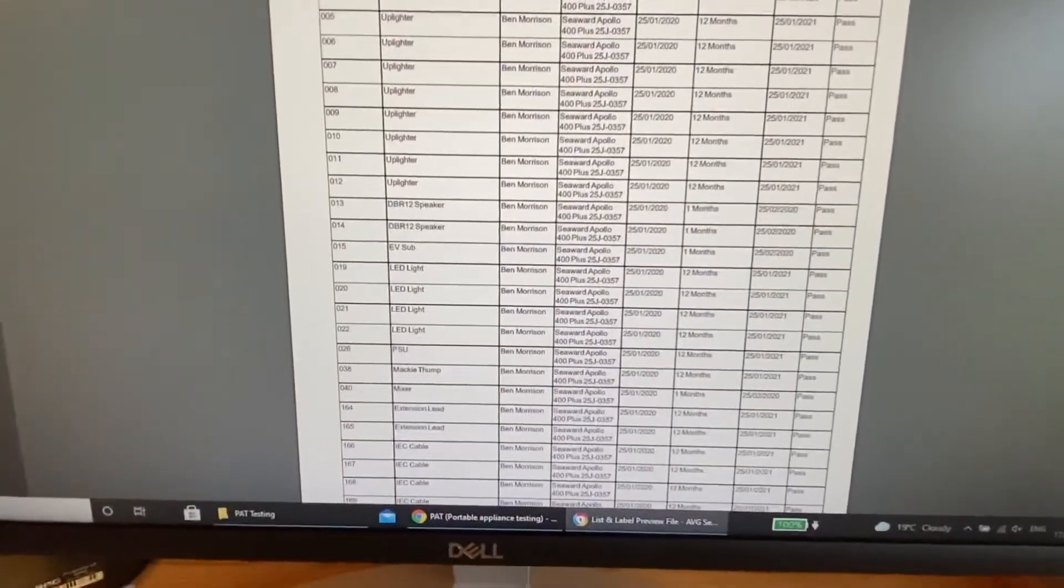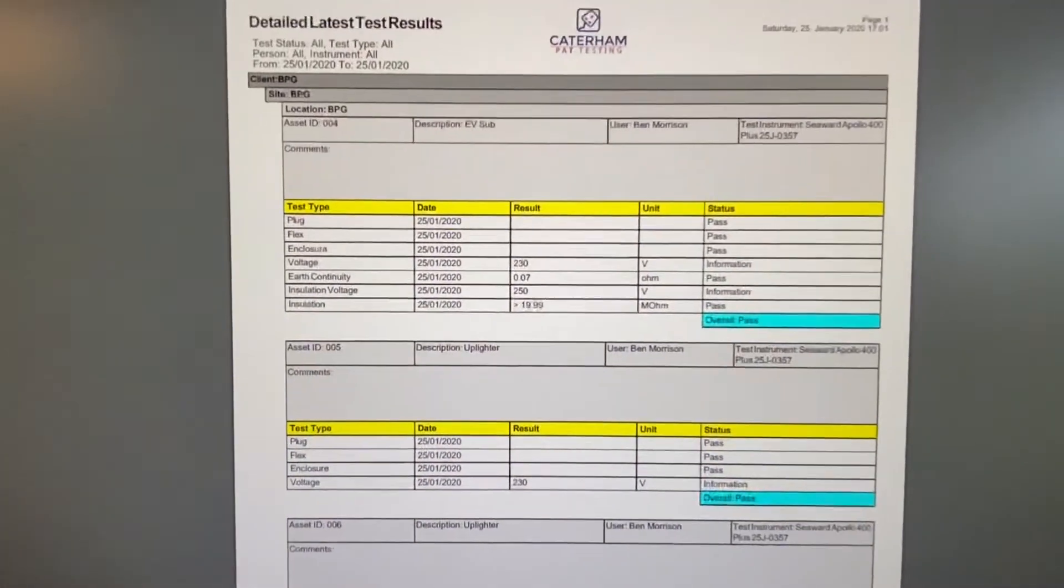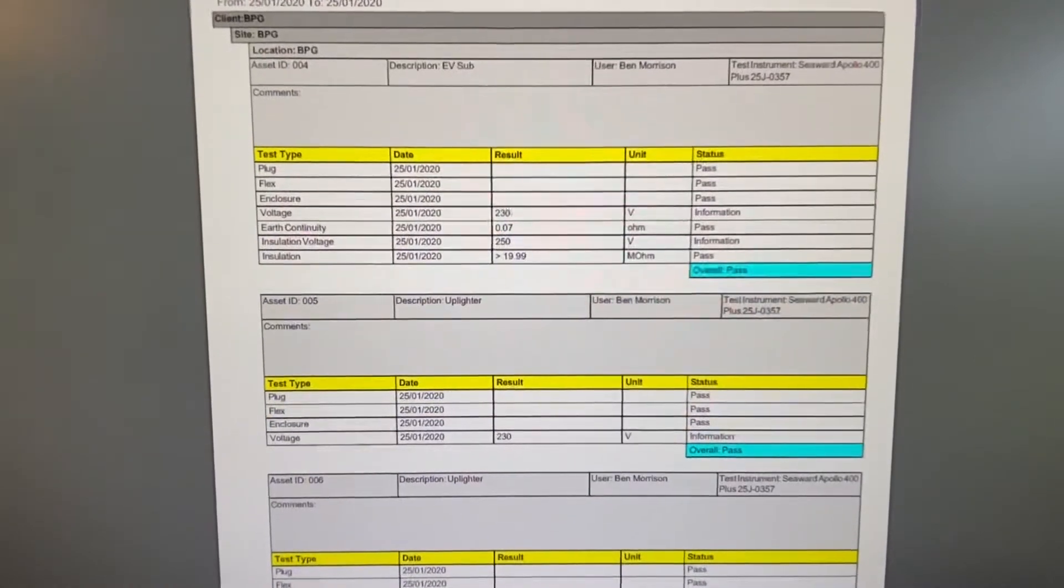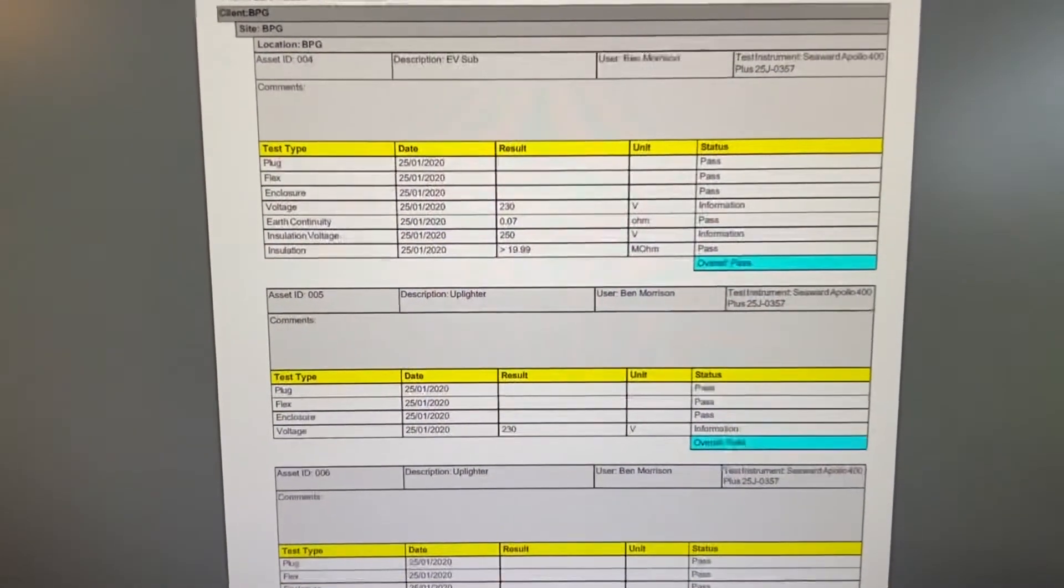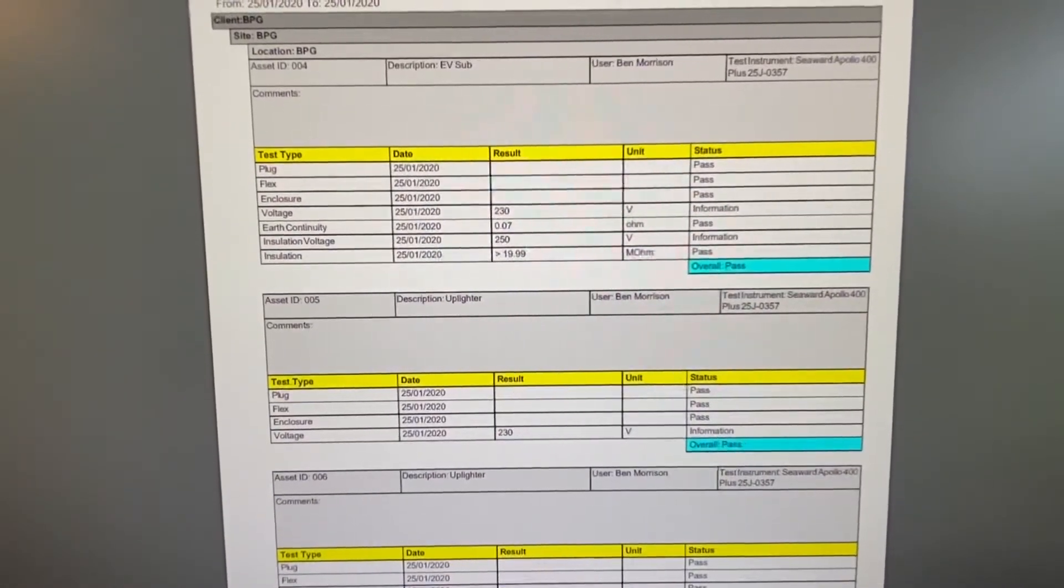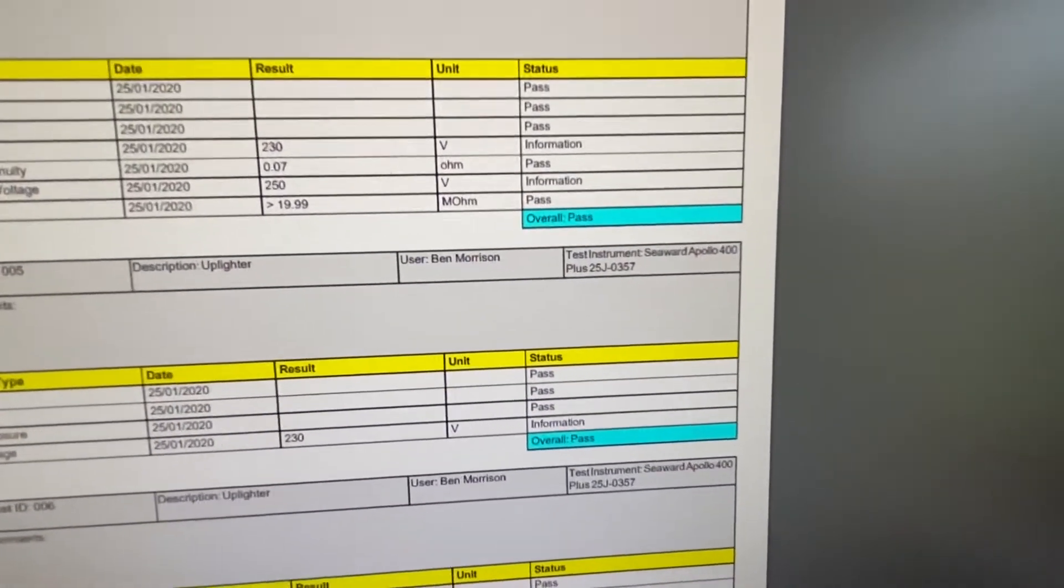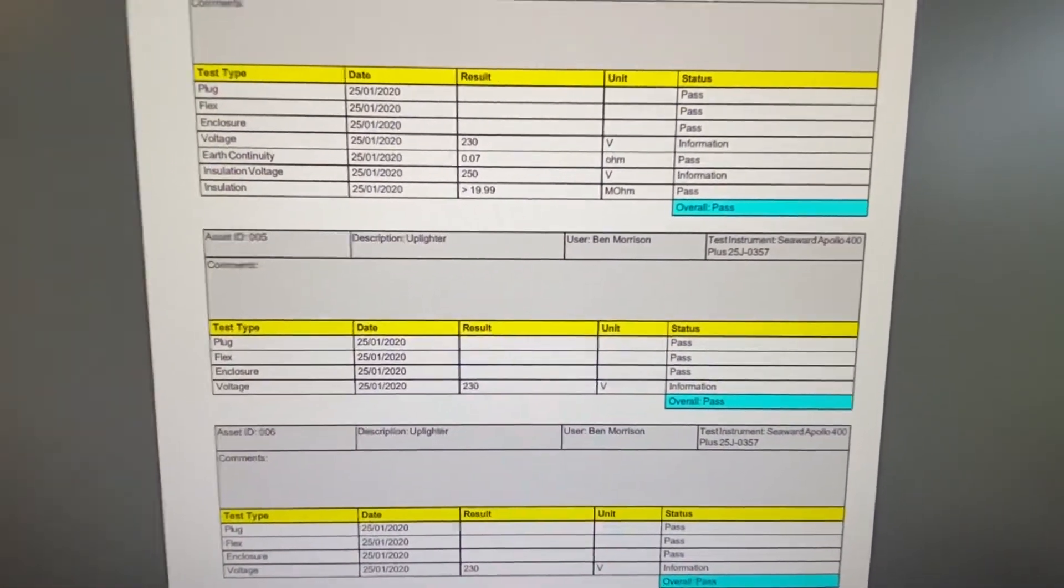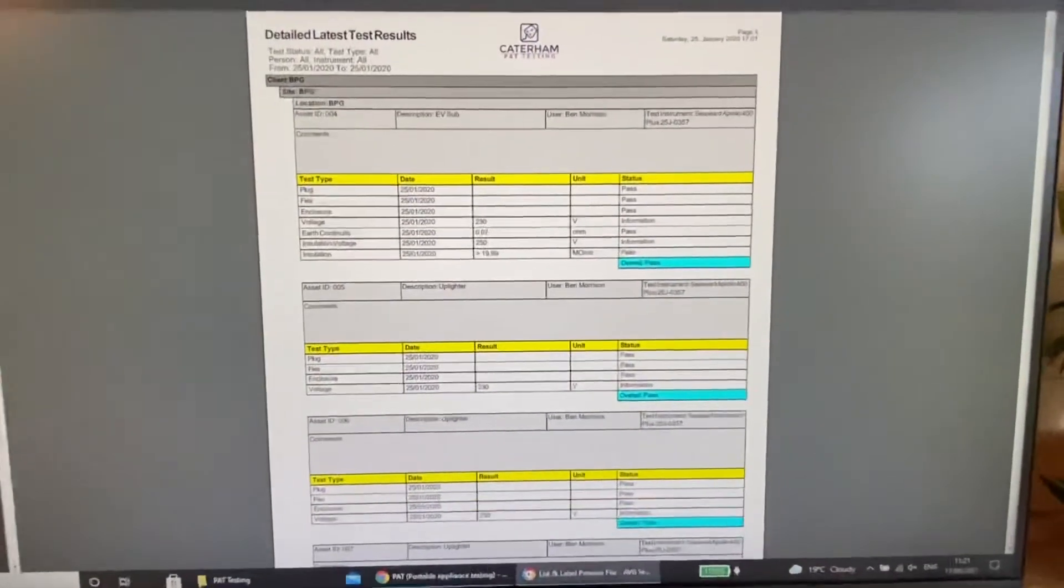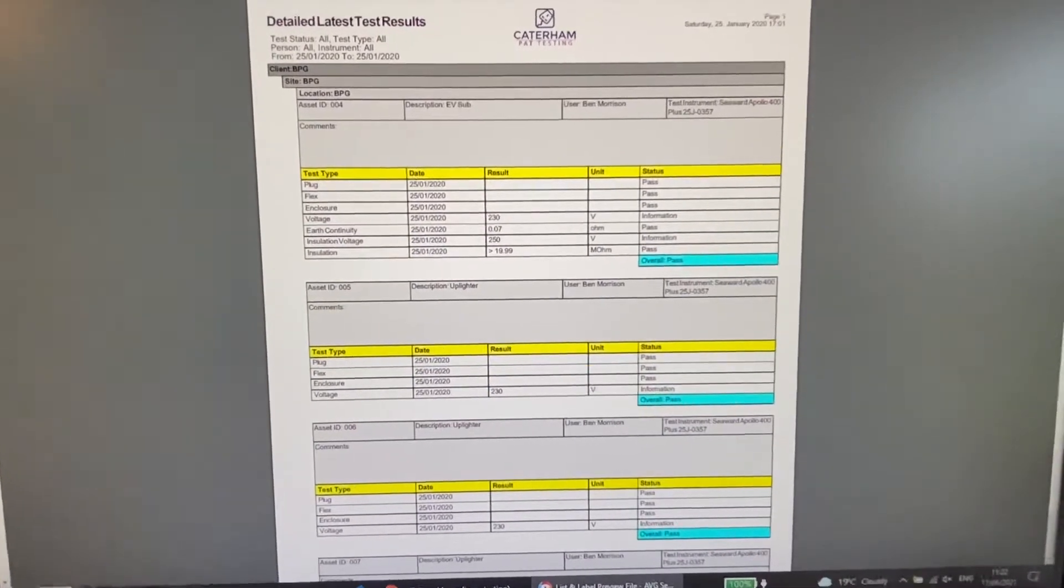And if I just click on here, you can also do a detailed test list. And this basically, on this piece of software, it gives every single test that is done. So the earth continuity test, the visual inspection, the insulation resistance test, and then overall pass. It gives you the test machine that it was done from and the asset ID and any comments as well that you want to put in. So obviously with this PATGuard 3 software, there is a cost involved.